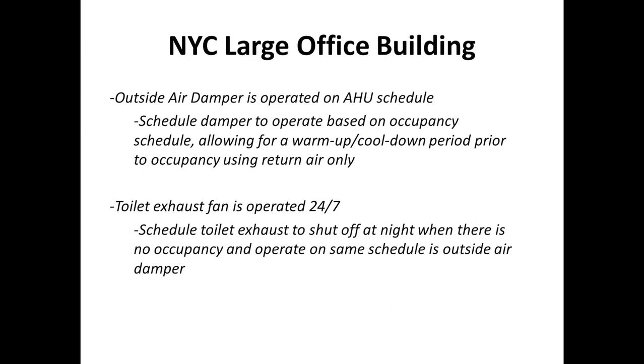Likewise, we could install data loggers on the toilet exhaust fan. It was hooked up to the BMS system, but no one was really sure how it was controlled or if it was actually turning on or off at night. There's a schedule inputted in there that was grayed out. We were there during the day, so we couldn't observe it at night. We installed motor on/off HOBO data loggers and were able to see that the exhaust fan actually doesn't turn off. It remains on 24/7. So this building could hire the BMS controls contractor to adjust the schedule and shut off the exhaust fan in accordance with the outside air damper, so that it only comes on when there's actually occupancy in the building.